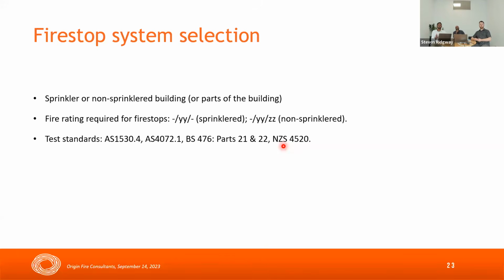What manufacturers do is they take their product, their system, and they go to an accredited fire test laboratory, and then they test it according to this standard, and they record what happened. They give you a fire test report, and that tells you what standard it's been tested to, what rating that fire stop has achieved, and how it was installed. So we get that information from a manufacturer.